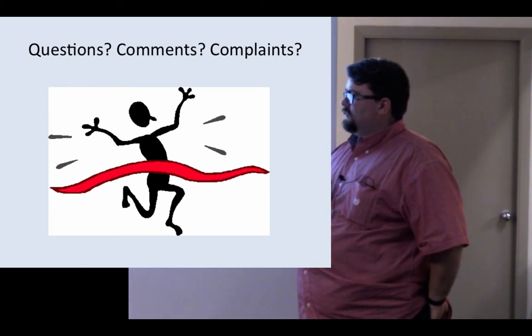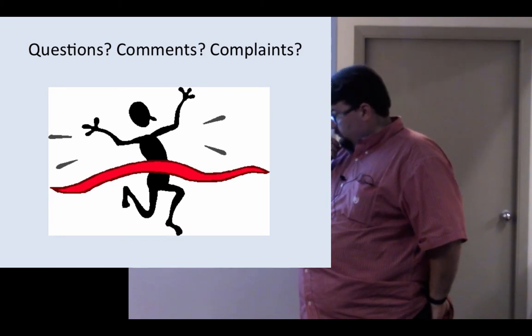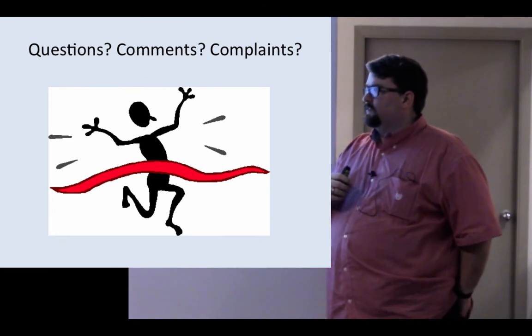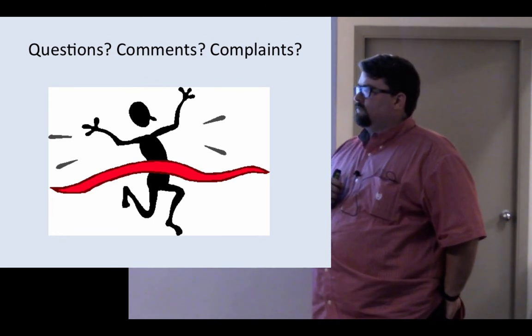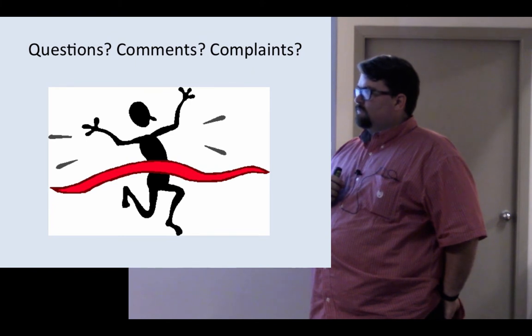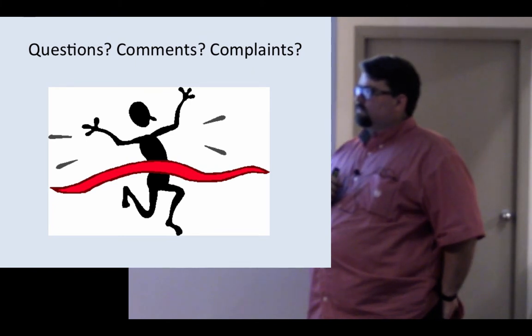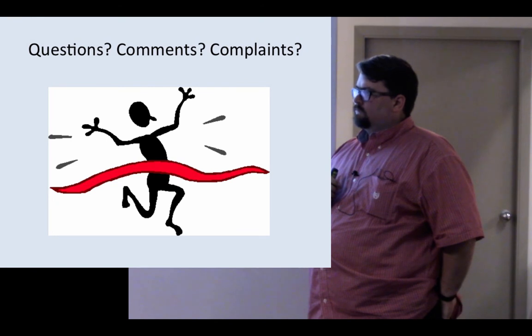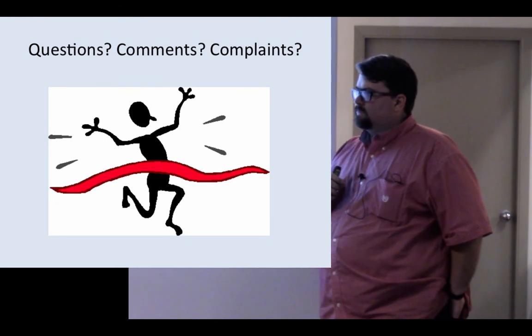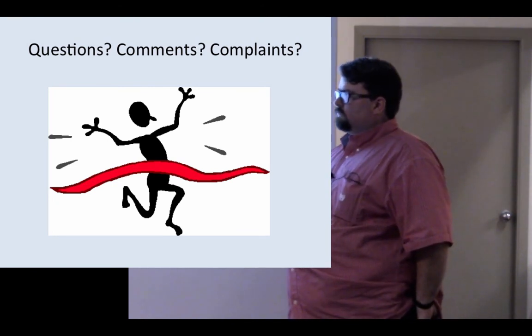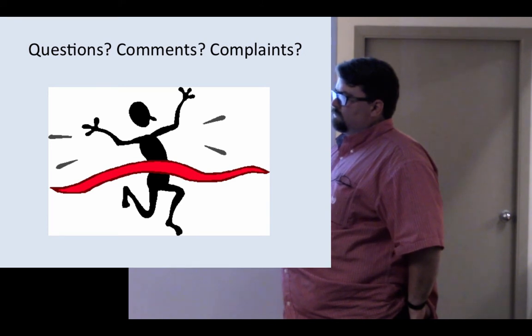It depends, actually more importantly, on whether there's a safety issue involved, because we're talking medical, right? So we actually start right out of the gate with a preliminary hazard analysis. So even when we're just scoping out the project, based on the scope of what functionality is going to be introduced, we conduct a preliminary hazard analysis, and that tells us where our general areas are that we need to focus our attention. Then that gets drilled down into a product risk assessment, where we're identifying our risk control measures.